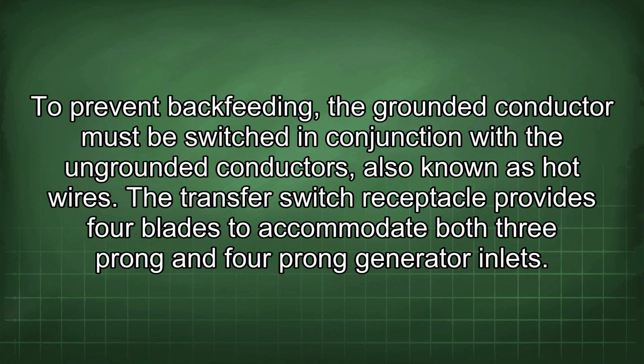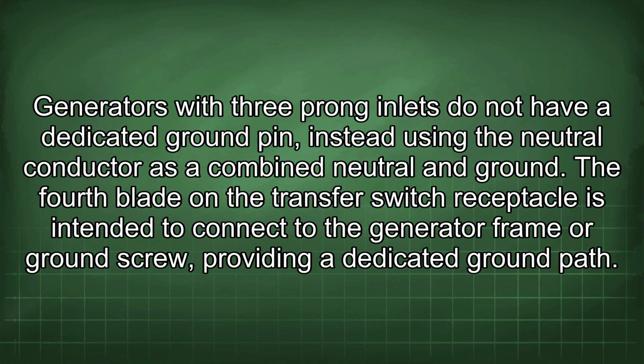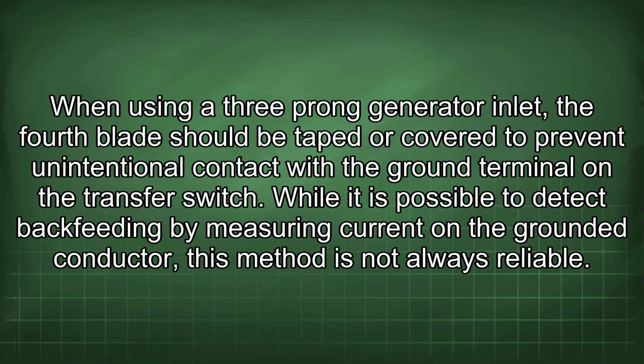The transfer switch receptacle provides 4 blades to accommodate both 3-prong and 4-prong generator inlets. Generators with 3-prong inlets do not have a dedicated ground pin, instead using the neutral conductor as a combined neutral and ground. The 4th blade on the transfer switch receptacle is intended to connect to the generator frame or ground screw, providing a dedicated ground path. When using a 3-prong generator inlet, the 4th blade should be taped or covered to prevent unintentional contact with the ground terminal on the transfer switch.